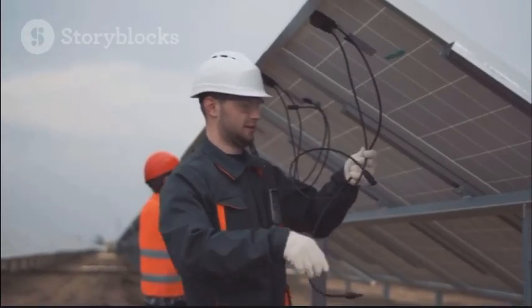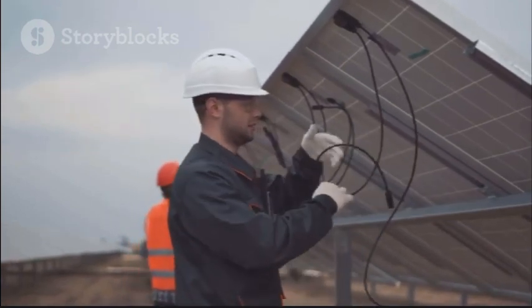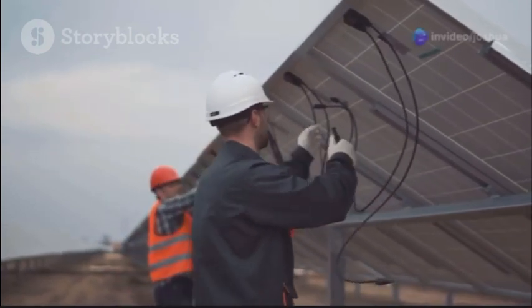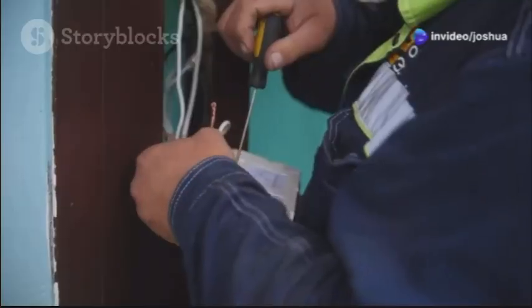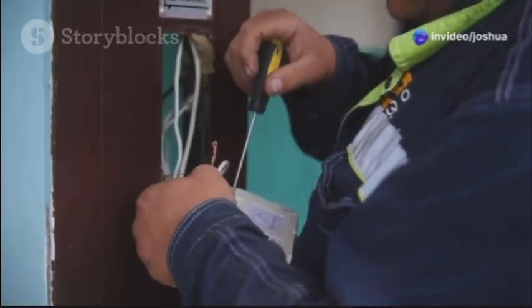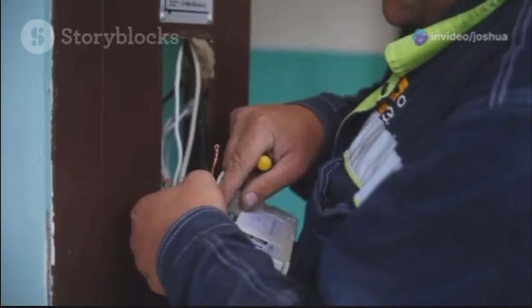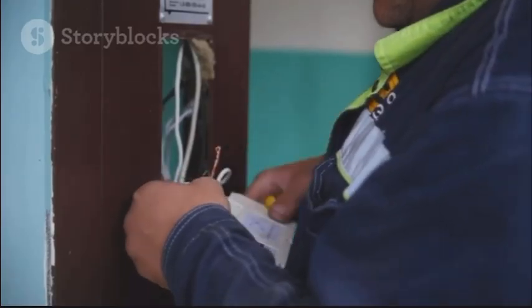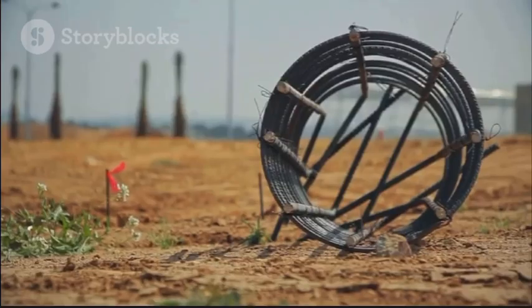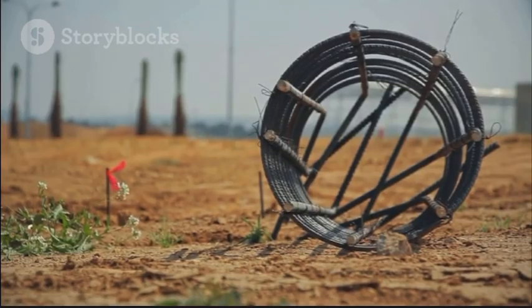Finally, step 5. Ground control. Proper grounding is essential for both safety and system reliability. Properly ground the inverter and the mounting structure to prevent electrical shocks. This also helps protect your equipment from lightning and surges. Connect the grounding wire to a grounding rod driven into the earth. Remember, safety first. Never skip this step.